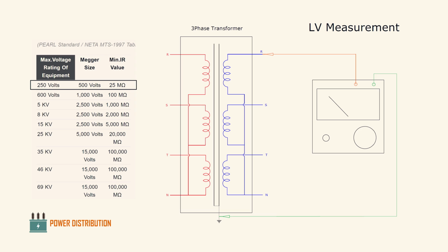The same treatment applies to the secondary windings. In order to measure the insulation level, we connect the line or hot probe into any of these secondary terminals, and then the earth terminal to the ground connection of the transformer. The minimum insulation resistance value we seek is around 25 million ohms for this particular transformer.